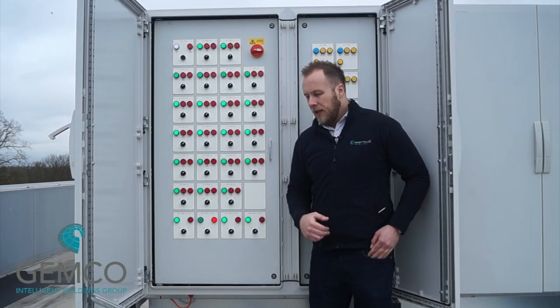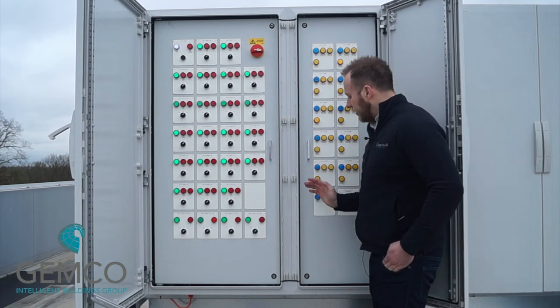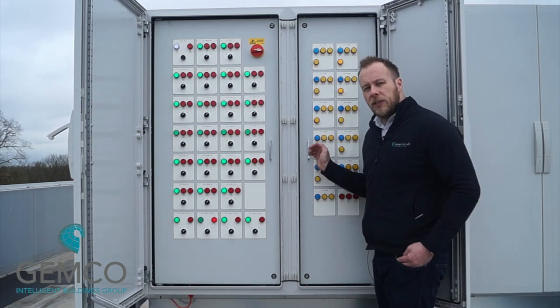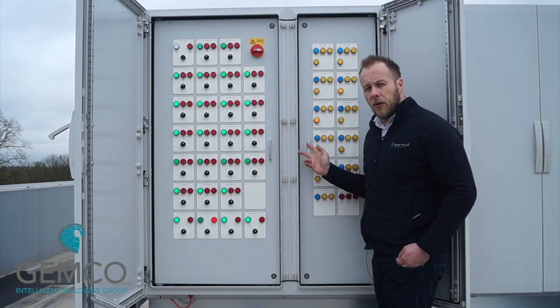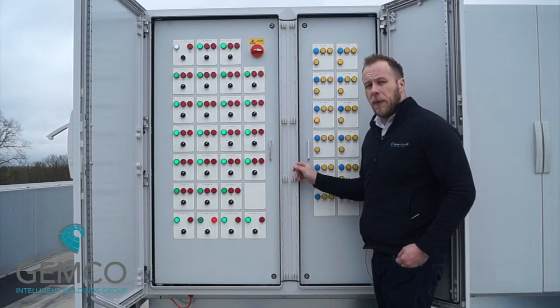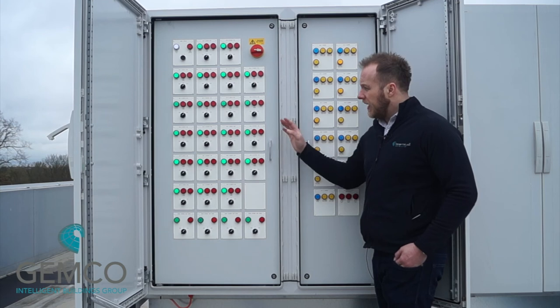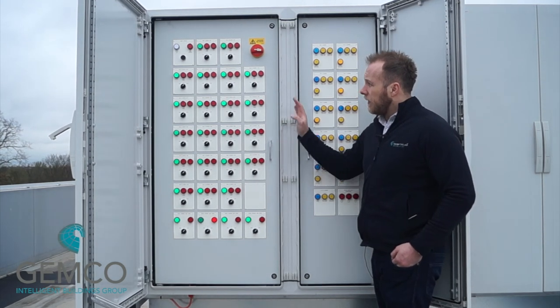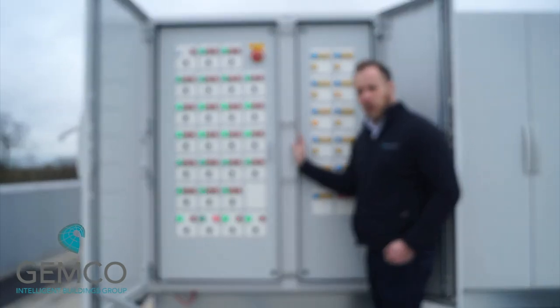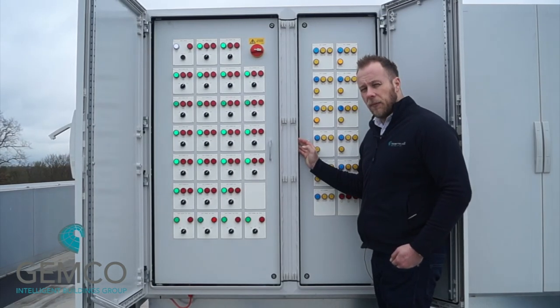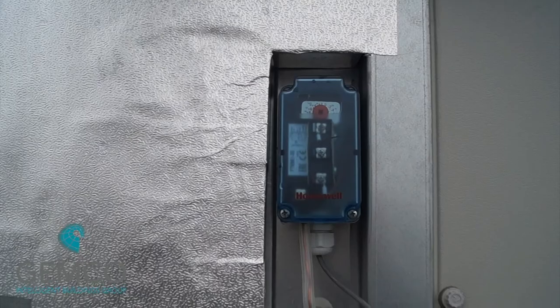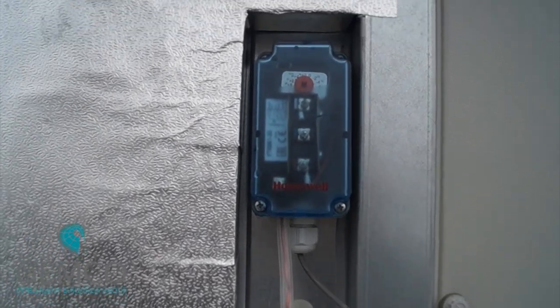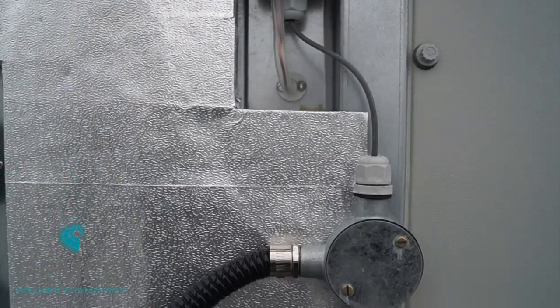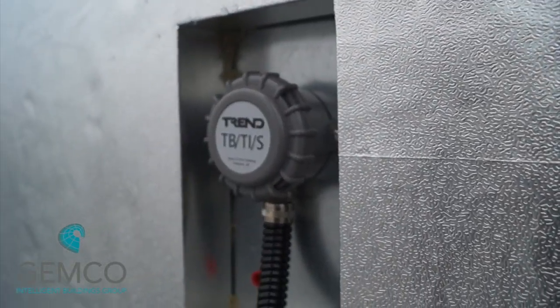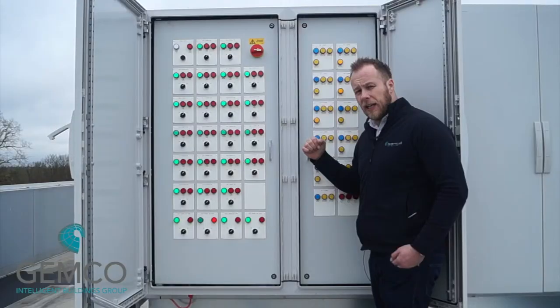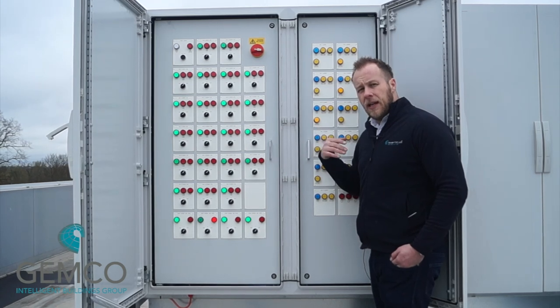It might take a while for the fan to ramp up and then the light to go out. Now if we move over to this section here, this section's just for monitoring, and this is where we monitor all of the frost alarms and the filter alarms. If there's no other safety circuits activated or in fault, the only other thing that will stop the air handling units running is a frost stat. On each of the air handling units, there's a hardwired capillary frost stat, which is a hardwired safety circuit to stop the fan running. It won't allow the dampers to open if that is activated.